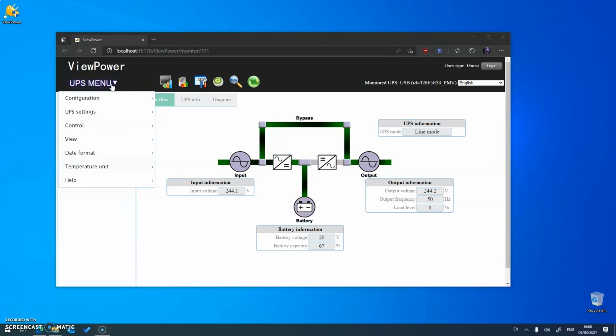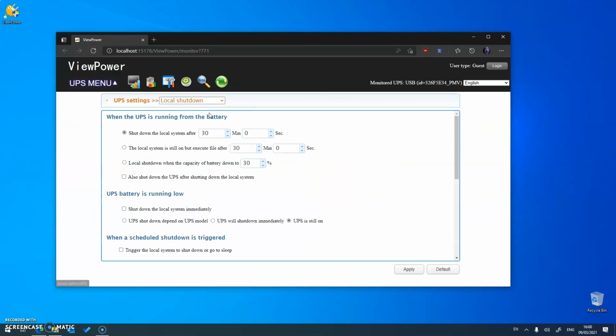You can choose at what point the UPS decides to shut down the host machine. To do that, go to UPS menu, UPS settings, and then local shutdown. There are various different ways you can shut down the UPS, and we'd recommend this option down here, which shuts down the host machine when the battery is 30% or less. The top option is good if you've got a very low load and know the UPS will definitely last over that time, but if you can't guarantee it, the best way is by battery capacity.